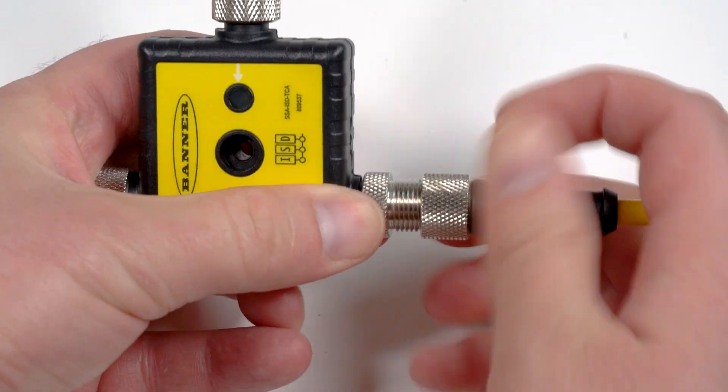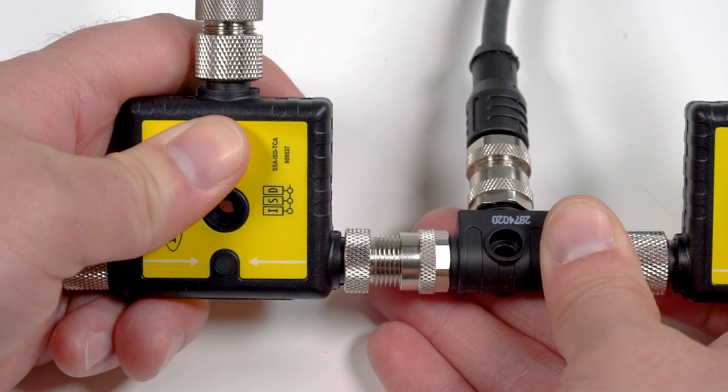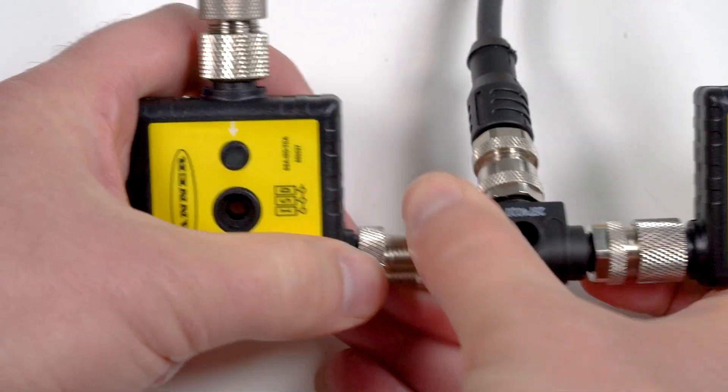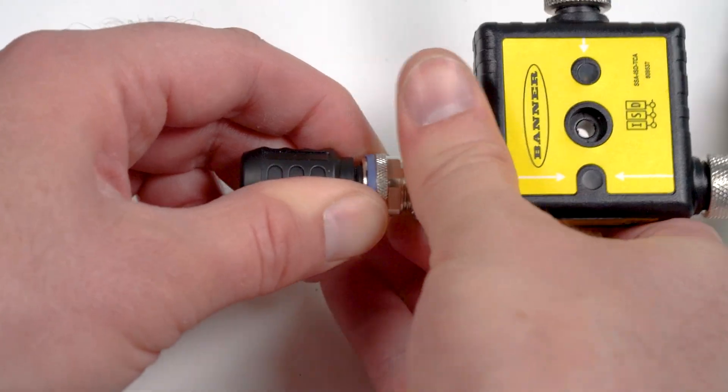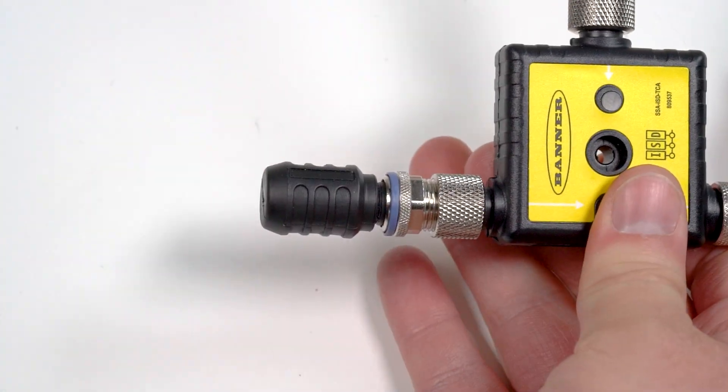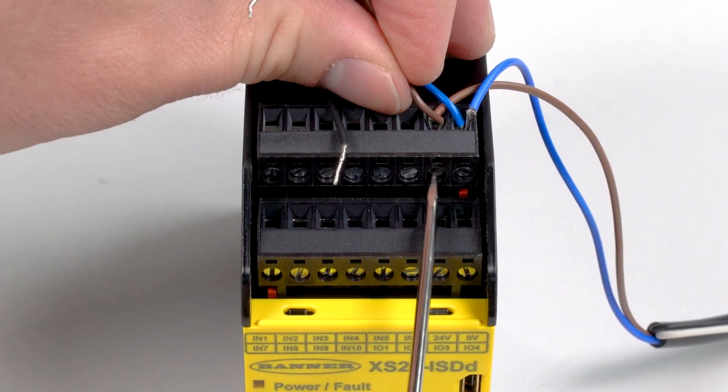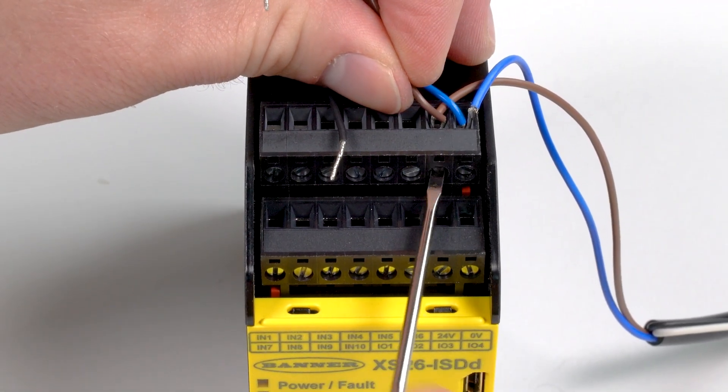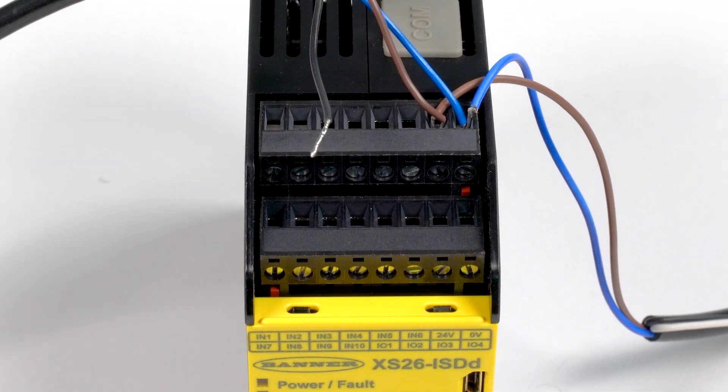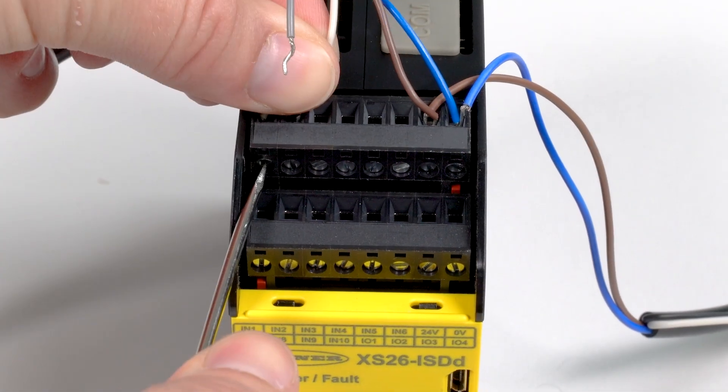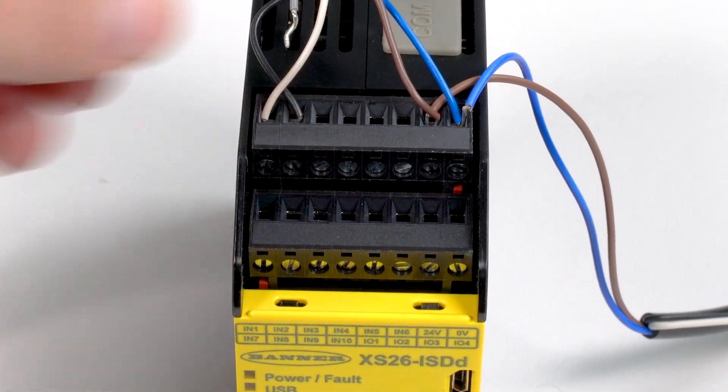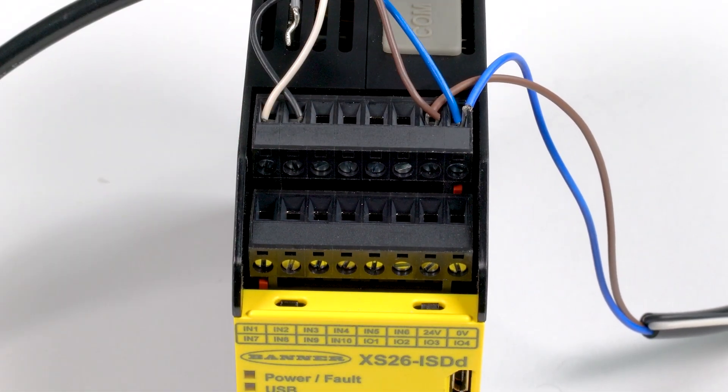When physically connecting the components, it's important to note that the chain requires a 24-volt DC power supply with the same ground as the safety controller. Each chain also requires two safety input terminals.